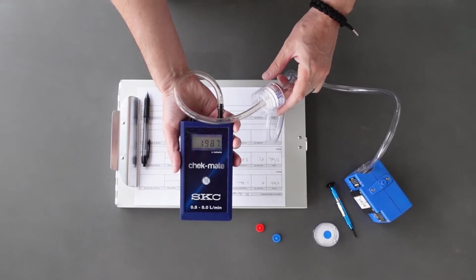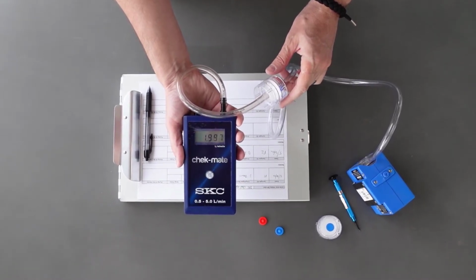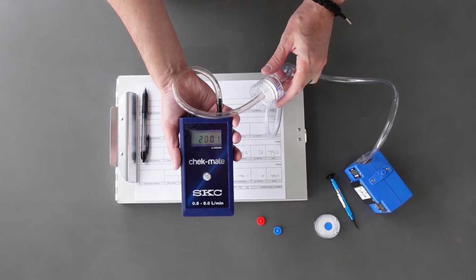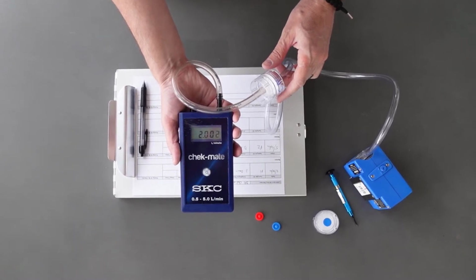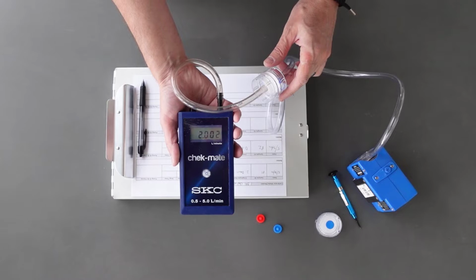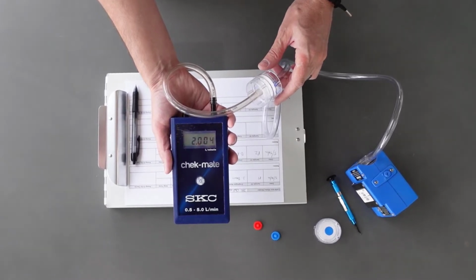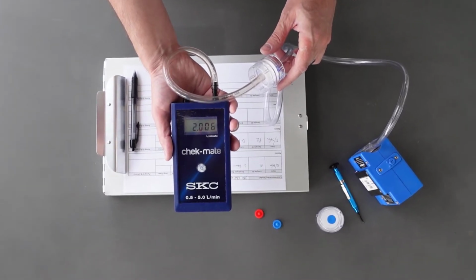Wait 30 seconds to a minute for the flow rate to stabilize. The targeted flow rate is approximately 2 liters per minute. You don't need to be exactly at 2 liters per minute. Any flow rate within 5 to 10% of 2 liters per minute is good enough.